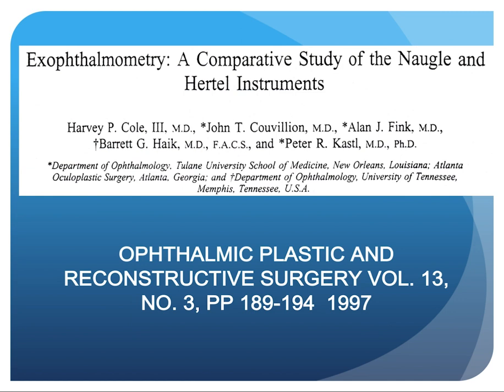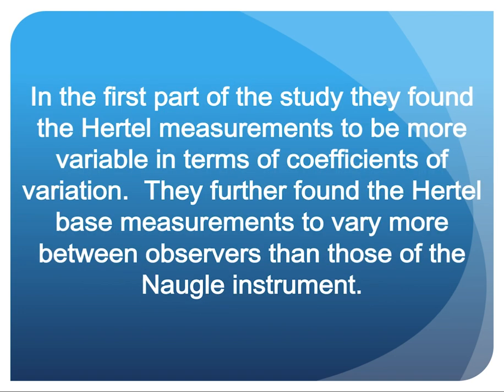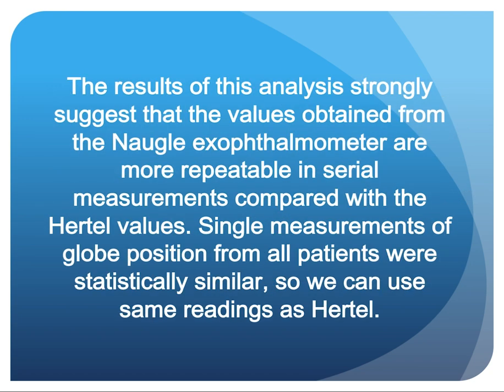There was an article in Ophthalmic Plastic and Reconstructive Surgery in 1997 entitled 'Exophthalmometry: A Comparative Study of the Naugle and Hertel Instruments' by Harvey Cole, John Couvillion, Alan Fink, Barrett Haik, and Peter Kastl MD PhD, who performed our biostatistics. They found the Hertel instruments to be more variable in coefficients of variation, and to vary more between observers than the Naugle instrument. The results strongly suggest that values obtained from the Naugle exophthalmometer are more repeatable in serial measurements. Single measurements of globe position from all patients were statistically similar, indicating we can use the same baseline readings as the Hertel.